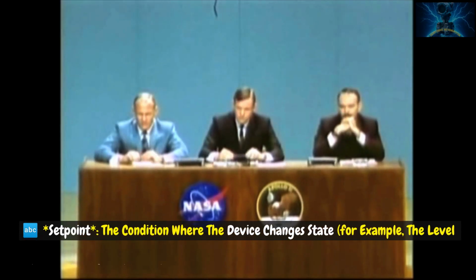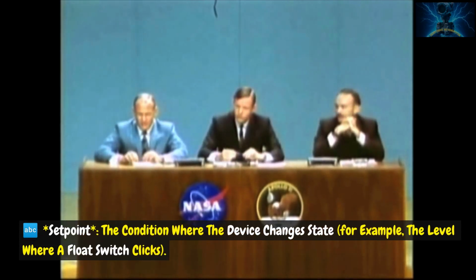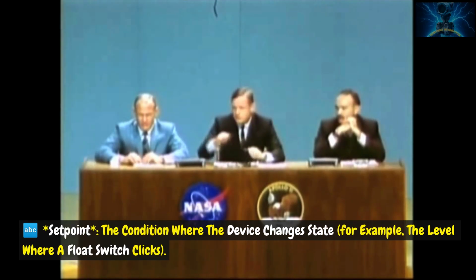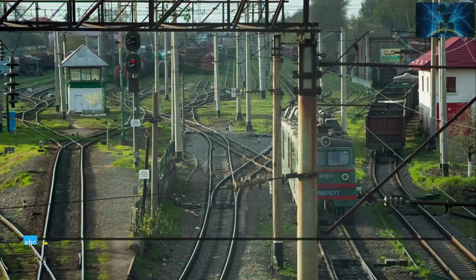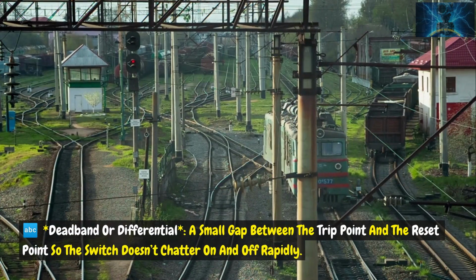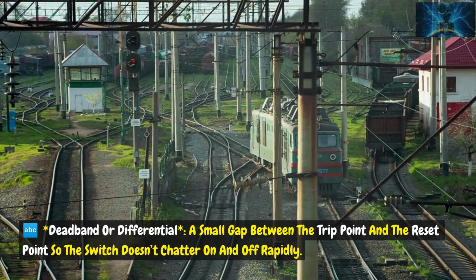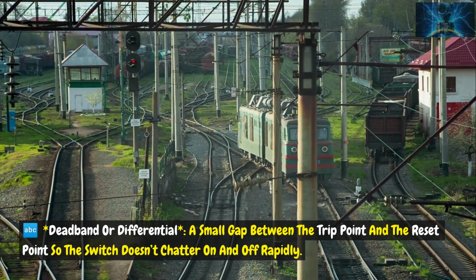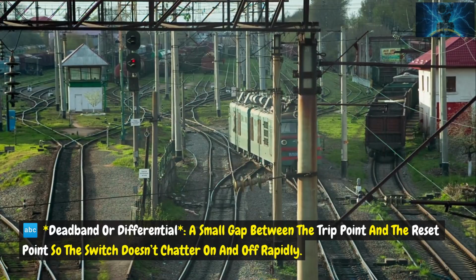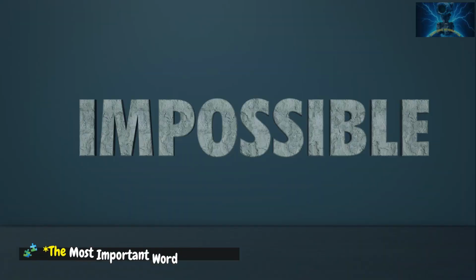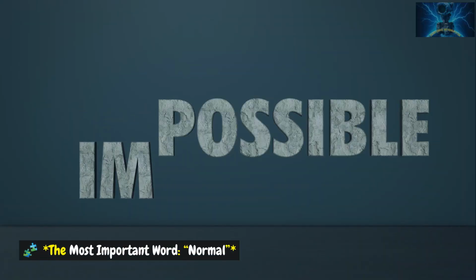Set point: the condition where the device changes state. For example, the level where a float switch clicks. Dead band or differential: a small gap between the trip point and the reset point, so the switch doesn't chatter on and off rapidly. The most important word: normal.